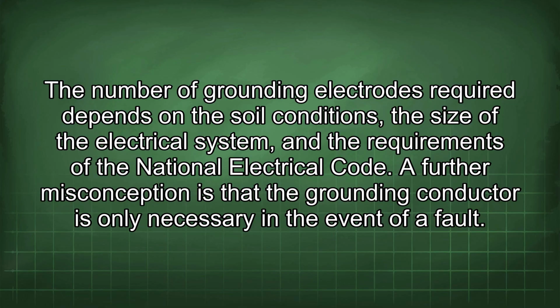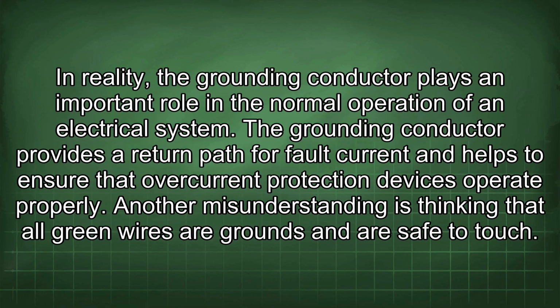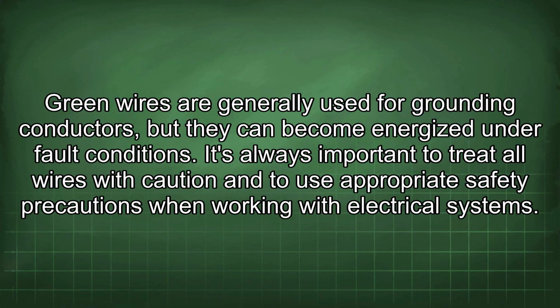A further misconception is that the grounding conductor is only necessary in the event of a fault. In reality, the grounding conductor plays an important role in the normal operation of an electrical system. The grounding conductor provides a return path for fault current and helps to ensure that overcurrent protection devices operate properly. Another misunderstanding is thinking that all green wires are grounds and are safe to touch. Green wires are generally used for grounding conductors, but they can become energized under fault conditions. It's always important to treat all wires with caution and to use appropriate safety precautions when working with electrical systems.